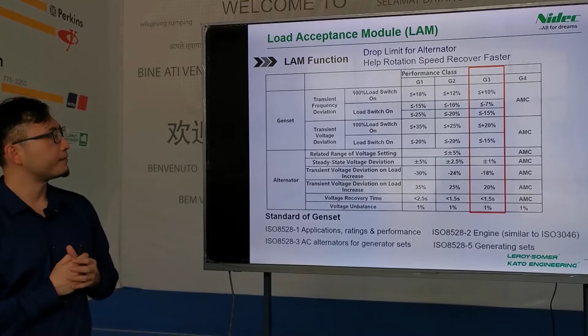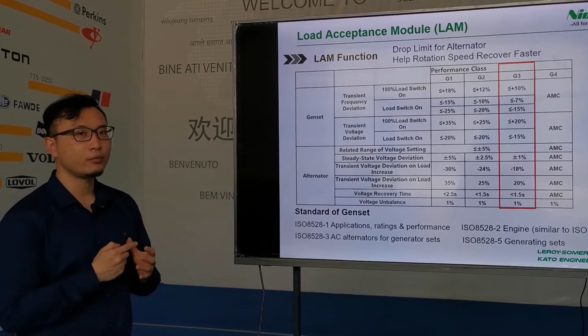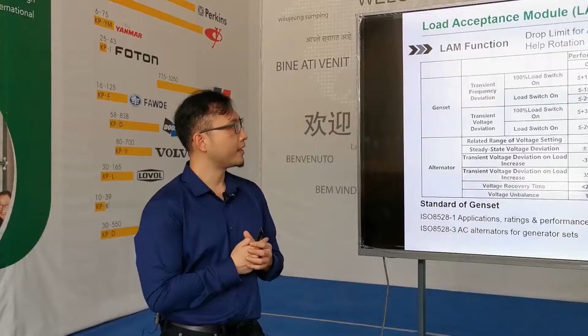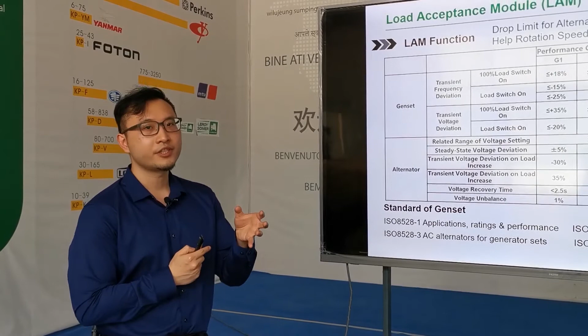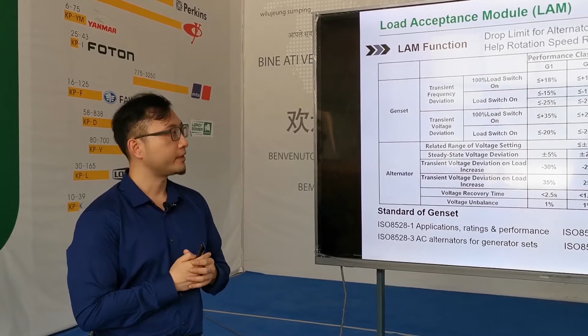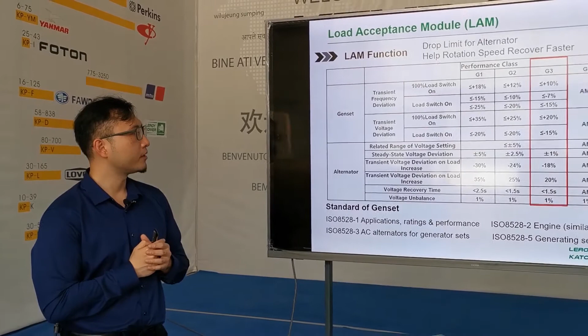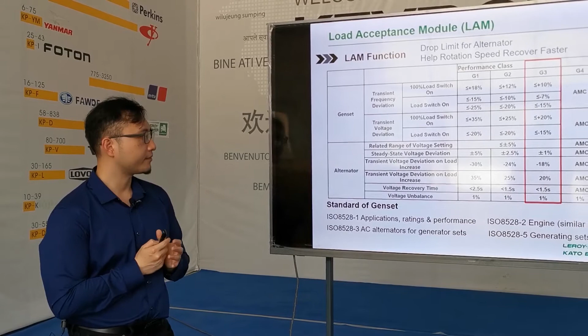It's mainly a function that helps the machine, when it suddenly gets an impact load, 100% impact load, recover the rotation speed, voltage and frequency to the rated level. It's quite helpful if the G3 or G2 standard is requested.